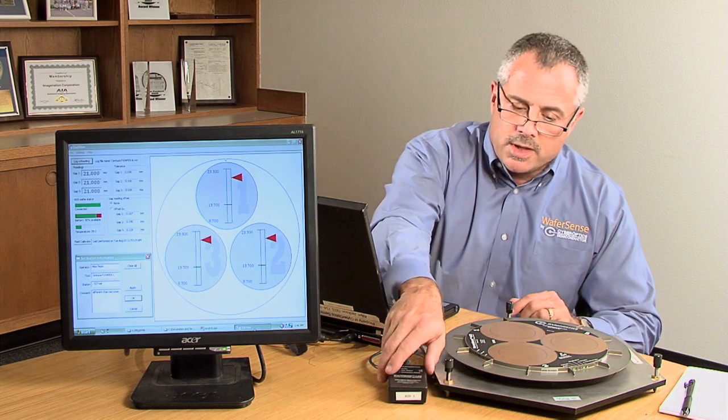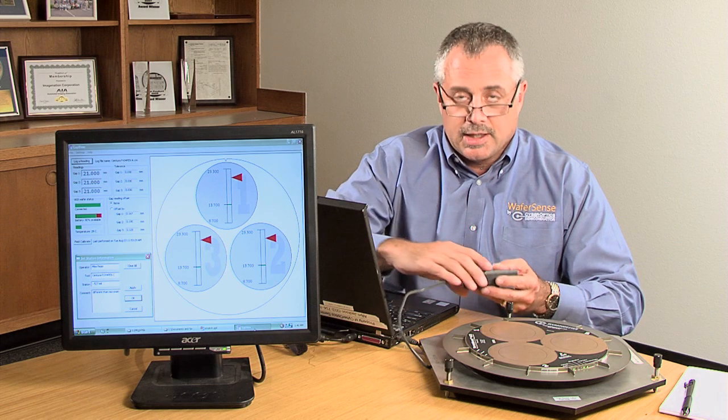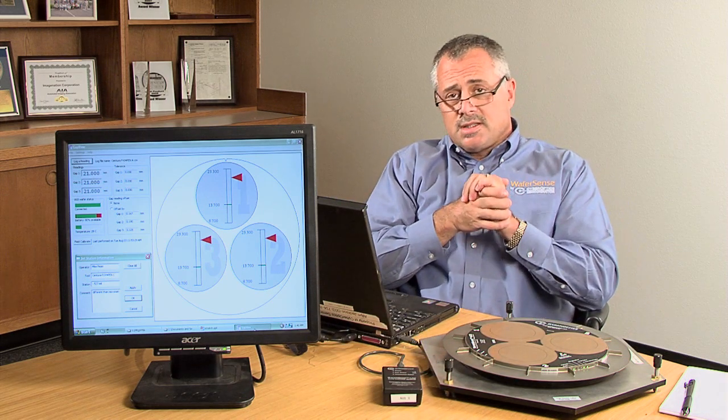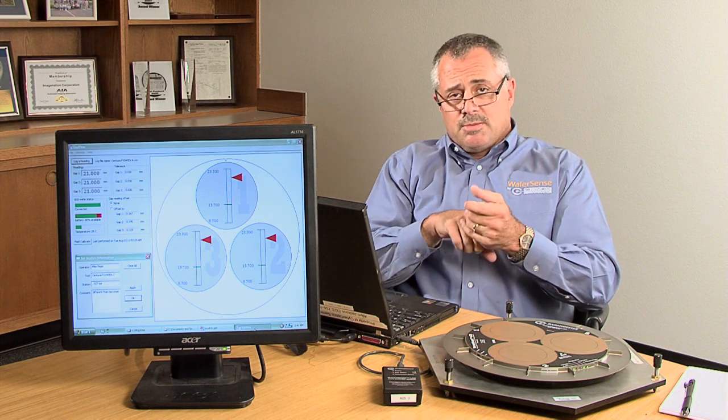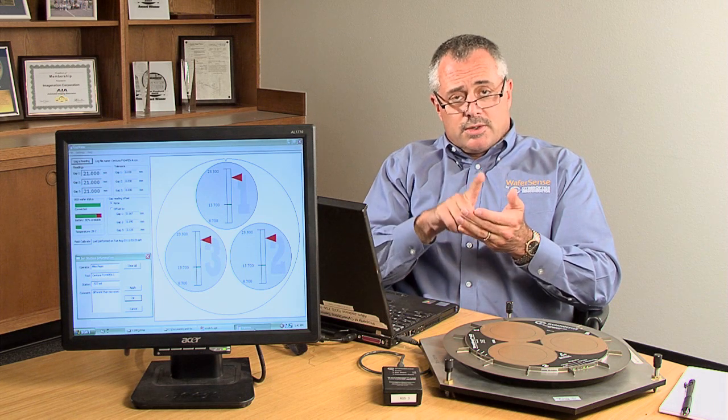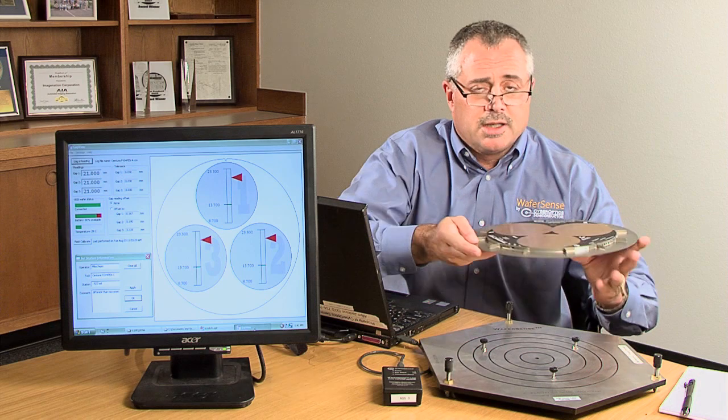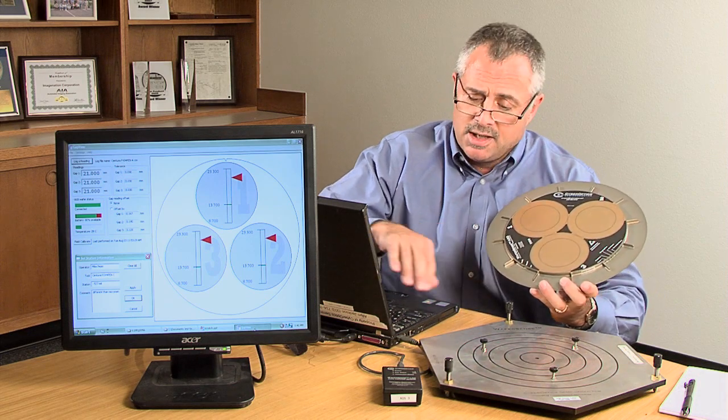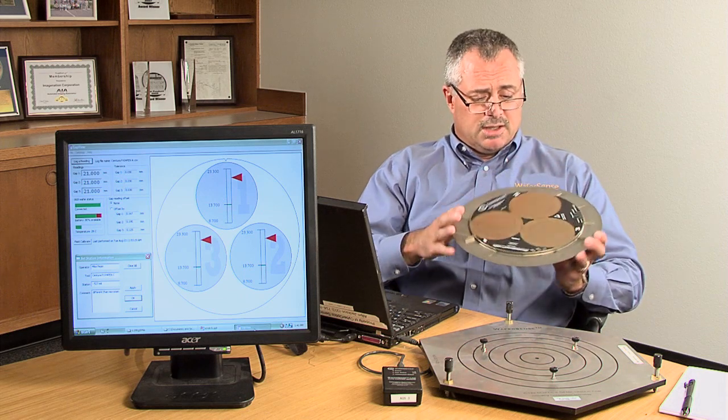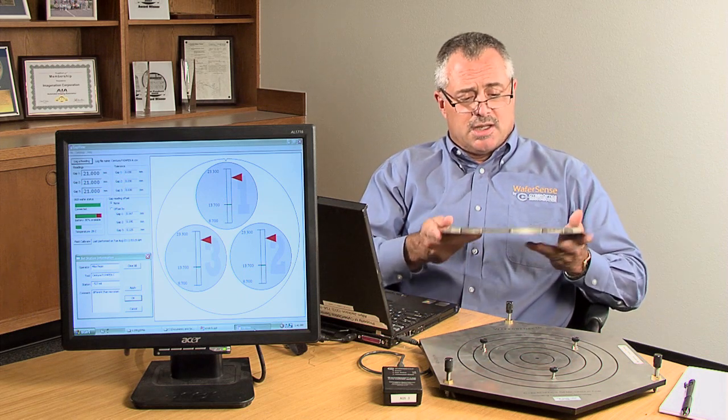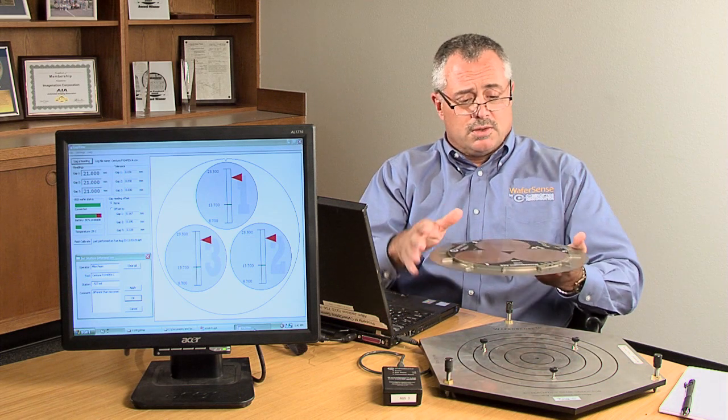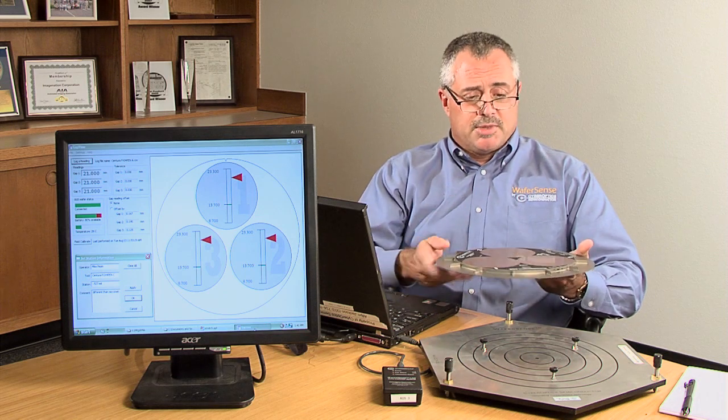The way you start up AGS is you plug in a link box into a Windows compatible system that can be either a laptop or the system console that runs anything from Windows 2000 up through Windows 7. You turn on the AGS wafer and establish a one-to-one Bluetooth wireless link communication. And with this wireless communication, the AGS wafer is able to travel inside a tool, a sealed tool, even under vacuum, and transmit out the gapping data.